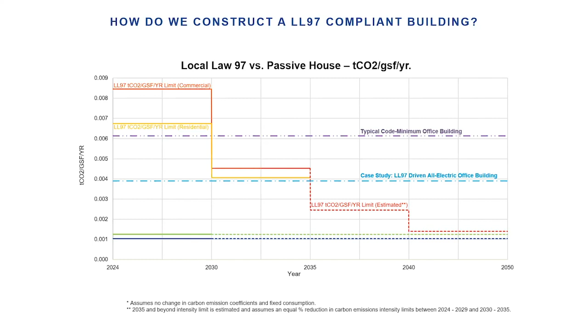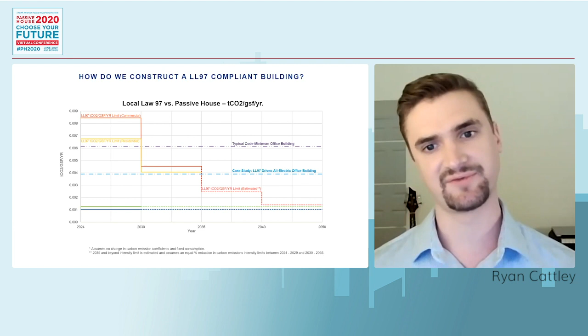So what we're seeing is a two-pronged approach to compliance with Local Law 97: short-term efficiency gains to try and avoid fines under the 2024 or 2030 limits, and designing a fully electrified building so that as the grid becomes increasingly renewable, buildings are less likely to face fines, since the carbon coefficient for electricity will, in theory, drop to zero with a fully renewable grid.